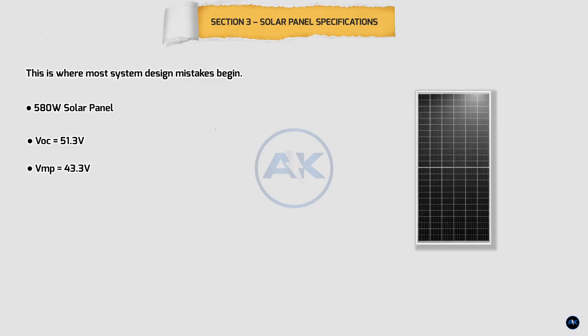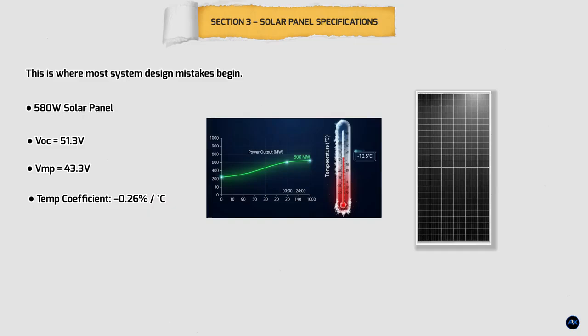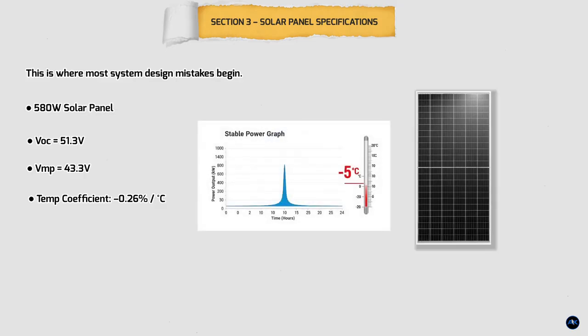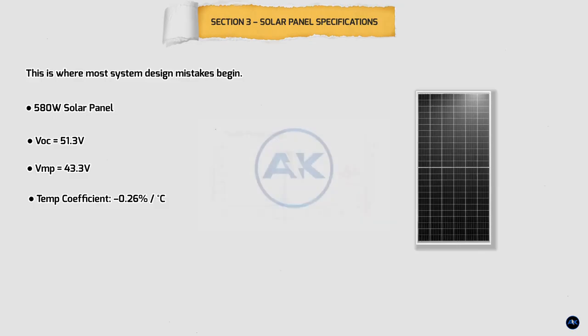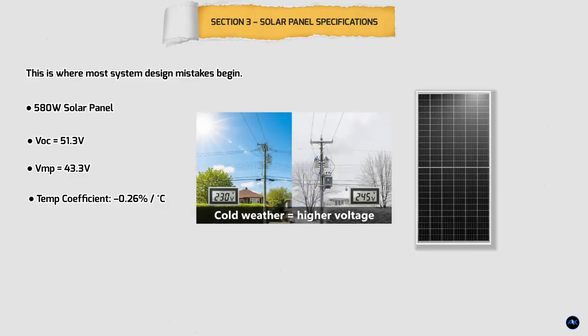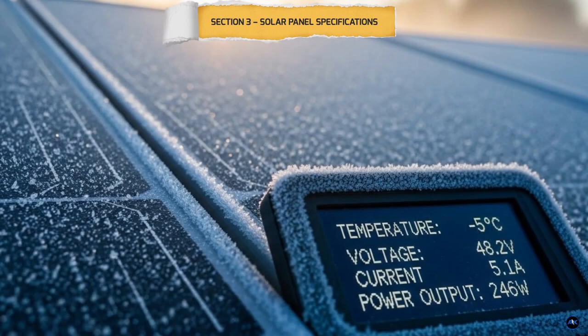Now, here's the most important and most misunderstood specification, the temperature coefficient of VOC. For these panels, the temperature coefficient is minus 0.26% per degree Celsius. What this means is simple. As temperature drops, voltage increases. On a cold winter morning, solar panels can produce much higher voltage than their rated value, even if the sun isn't very strong. This is why VOC and temperature coefficient matter far more than panel wattage when designing strings. Ignore this, and your system may work perfectly in summer, but fail catastrophically in winter. In the next section, we'll calculate exactly how cold weather affects these panels, and how many you can safely connect in series.